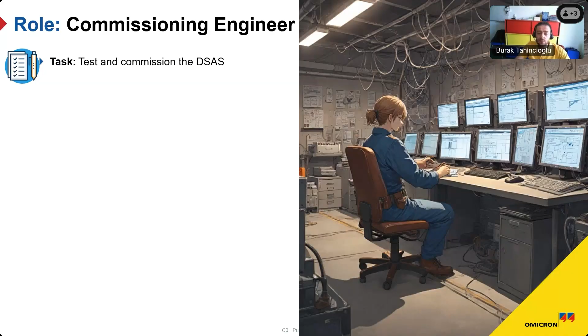And again, we take over the tasks or outputs from the previous role, the project engineer. They would have prepared an SCL file for us, and then we load this file to our IEDs, the devices, and execute the test files. There we would definitely use the IED configuration tools. We have nothing to do with the system configuration tool because that's done by our colleague previously, but we have the test devices nearby.